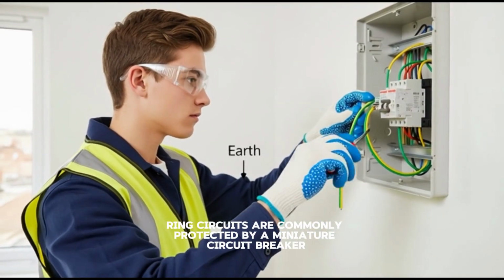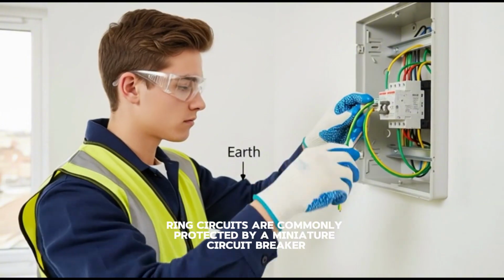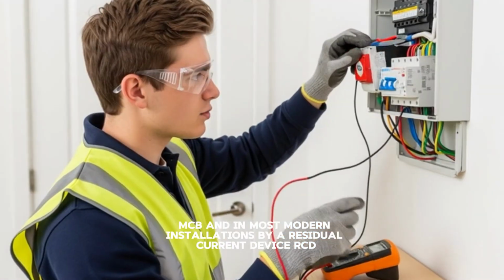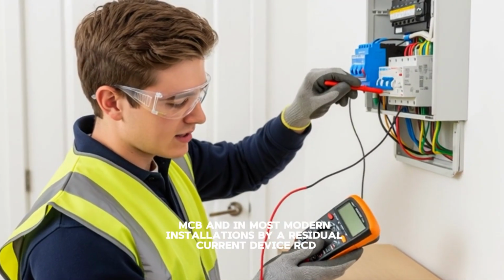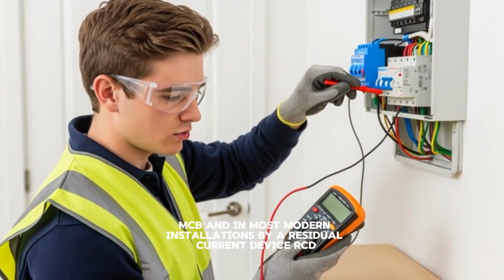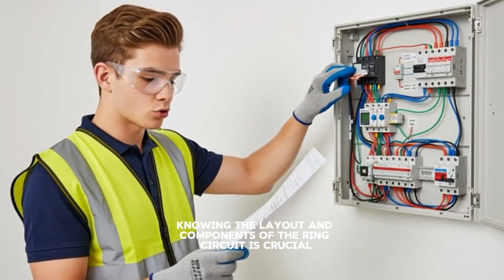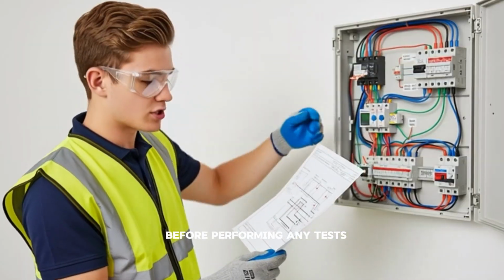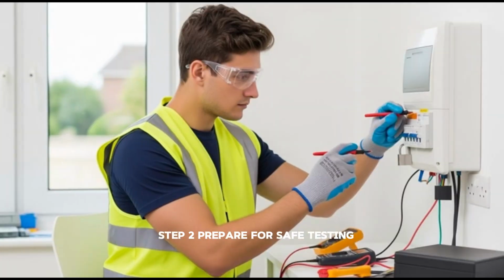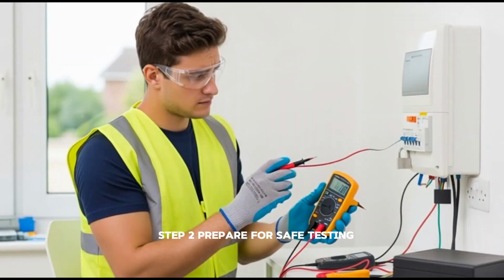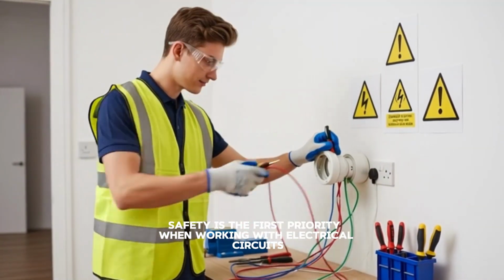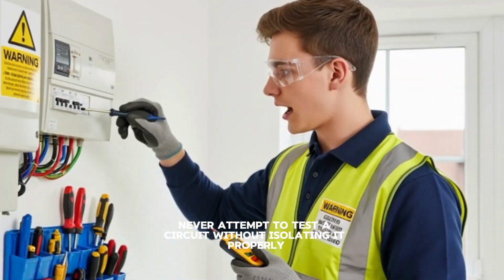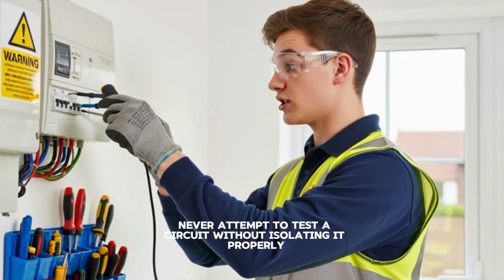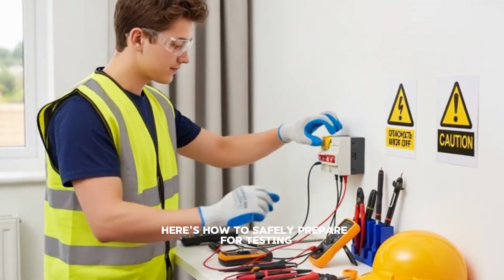Ring circuits are commonly protected by a miniature circuit breaker, MCB, and, in most modern installations, by a residual current device, RCD. Knowing the layout and components of the ring circuit is crucial before performing any tests. Step 2. Prepare for safe testing. Safety is the first priority when working with electrical circuits. Never attempt to test a circuit without isolating it properly. Here's how to safely prepare for testing.